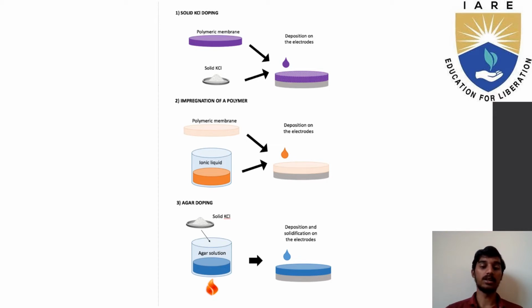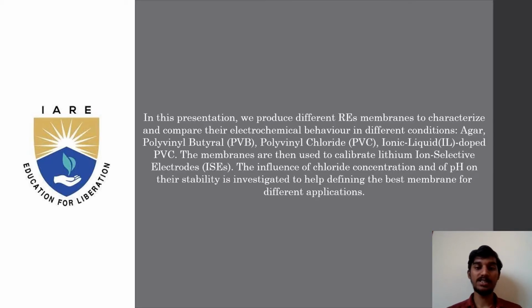In this presentation, we produce different RE membranes to characterize and compare the electrochemical behavior in different conditions: agar, polyvinyl butyral, polyvinyl chloride, ionic liquid doped PVC. The membranes are then used to calibrate lithium ion-selective electrodes, or ISE for short. The influence of chloride concentration and of pH on the stability is then investigated to help define the best membrane for the different applications.